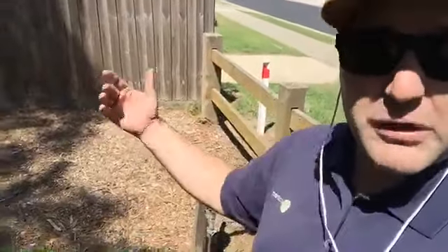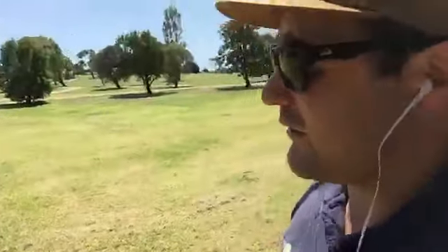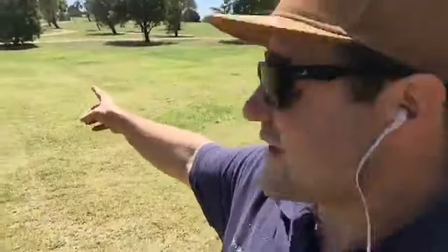Whenever it got put in, there was probably no need for it. But now all of a sudden someone's come past and said, we want you guys to put in an irrigation system. We'd come out here and ask, is there a water supply a little bit closer to the garden beds where we're going to be installing the irrigation? They say, yeah, there's a pipe that runs just in that bit of grass over there. We connect into that, and it's considered a commercial site, so we need to put in a minimum medium hazard device. We would choose a testable double check valve in that situation.